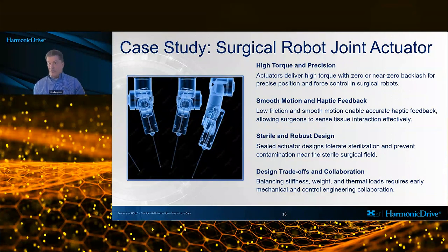These joints must deliver high torque in a compact envelope while maintaining zero or near zero backlash to support precise position and force control. Smooth motion and low friction are essential for accurate haptic feedback, which enables surgeons to sense tissue interaction. Additionally, joints are often located near the sterile field, requiring sealed designs that tolerate sterilization processes, or at a minimum prevent contamination. Strain wave-based integrated servo actuators are widely used in this context because they provide high reduction ratios, excellent torque density, and stable performance over time.